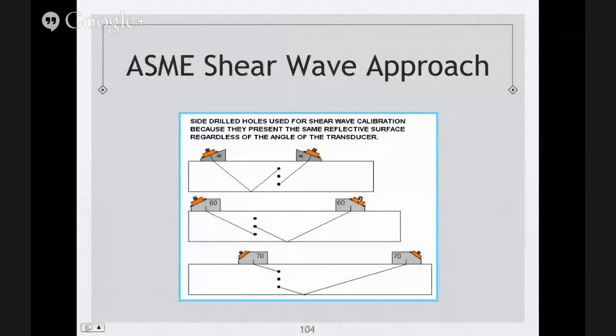So from here you measure, and we already know how to figure out the distance. We also know that, by having this 60 degree transducer and knowing the thickness of this plate, we can figure out how deep my indication went. And we could also figure it out even if it's not in the first leg, but also in the second.